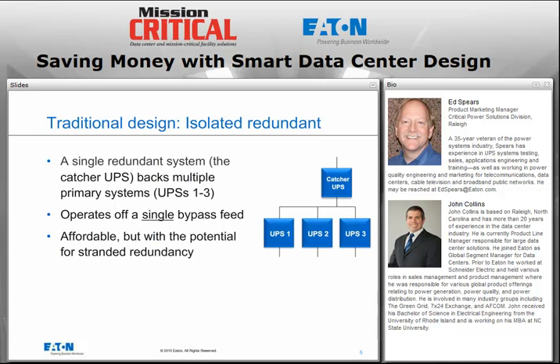So that's correct, and this next slide shows the traditional way that a catcher system was done. On the right-hand side of the slide, you see three primary UPSs along the bottom of the chart there, UPS 1, UPS 2, and UPS 3. And then above that, you see the catcher UPS, and the output of that UPS feeds the bypass input of the three primary UPSs. So you can see if, for example, UPS 2 were to develop a problem and needed to transfer to bypass power, when it did that, the catcher UPS would provide that bypass source along with conditioned power and battery backup. So it would provide that type of redundancy on the failure of any of the primary UPSs.